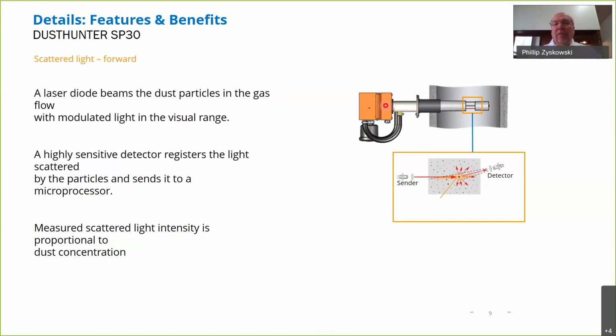Now, what we're calling forward scatter is occurring here in this measuring path. So our light beam is coming this way, our detector is this way, and what we're seeing is our light beam reflecting off of the front of the dust particles. So that's hence the forward scatter, forward or front.